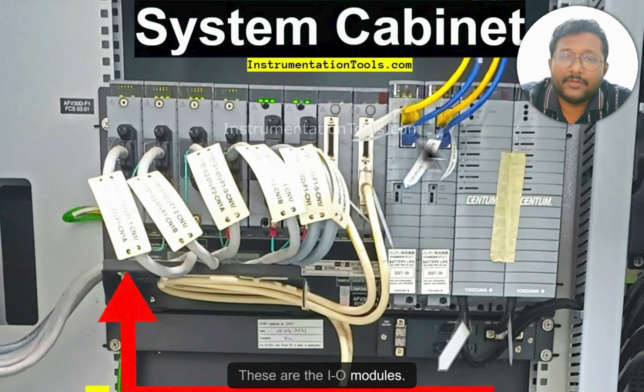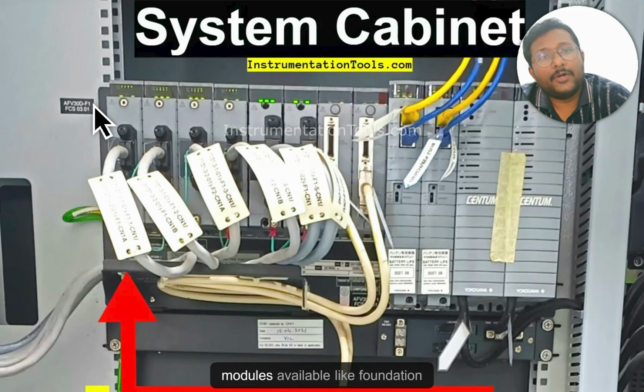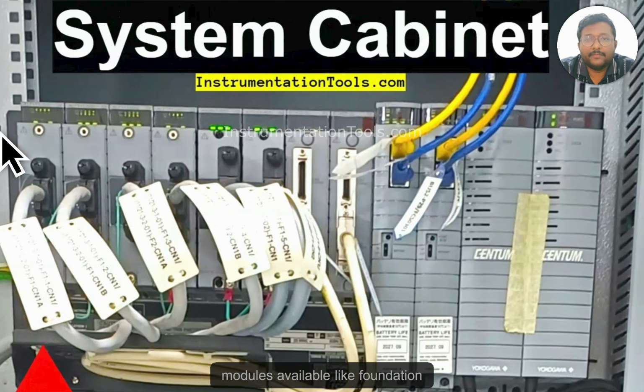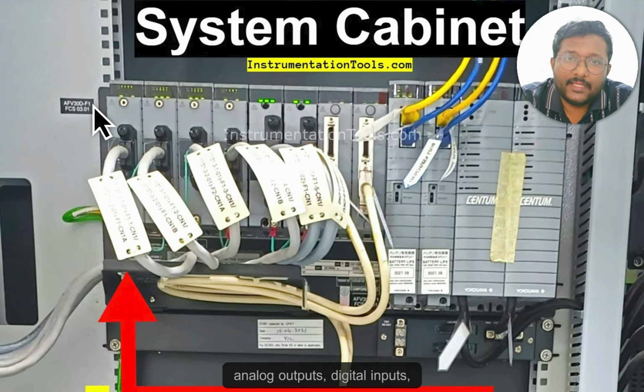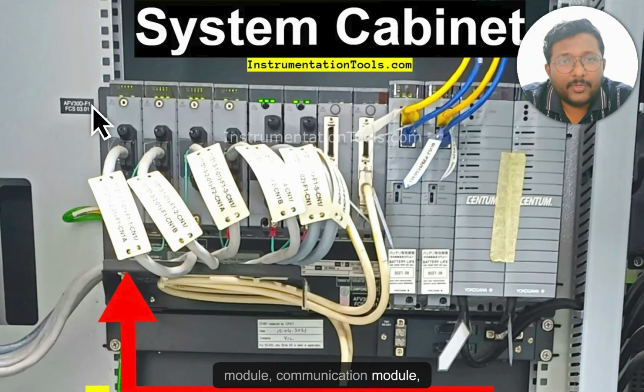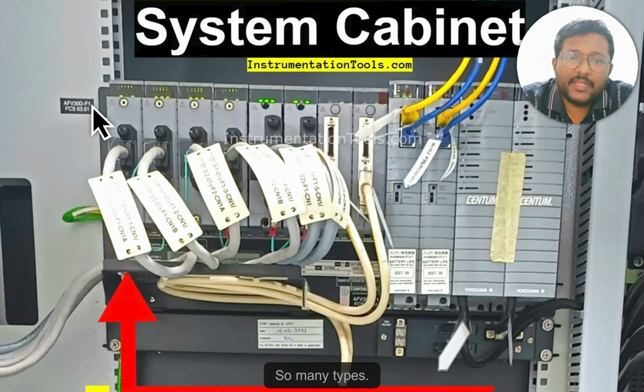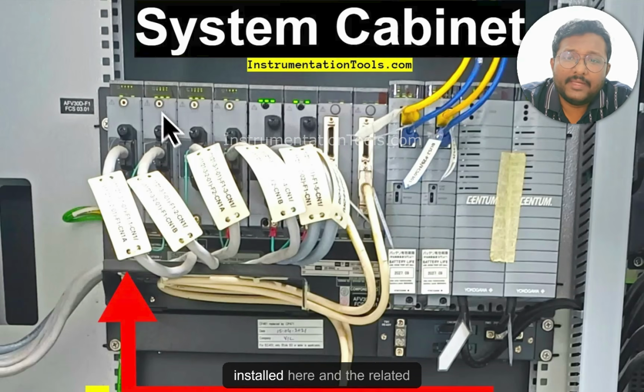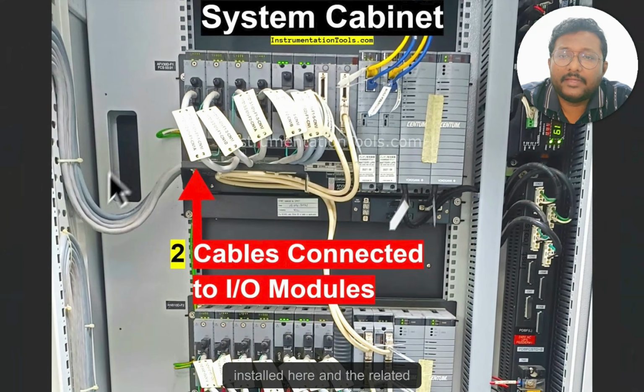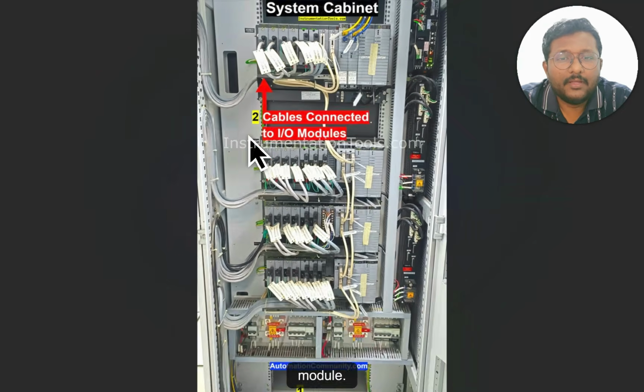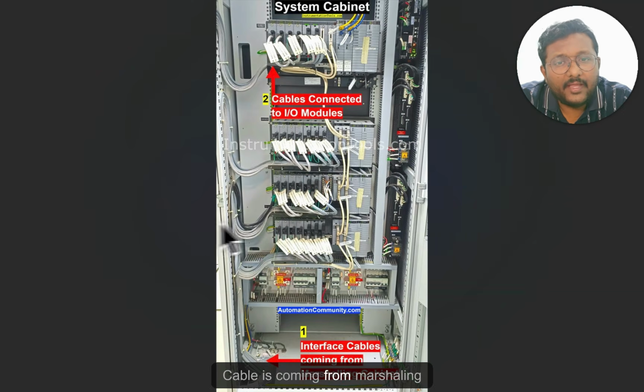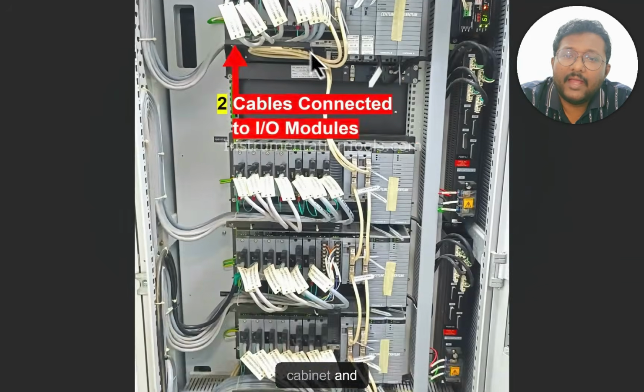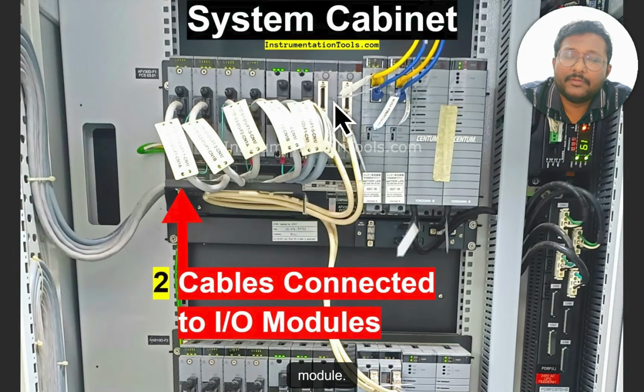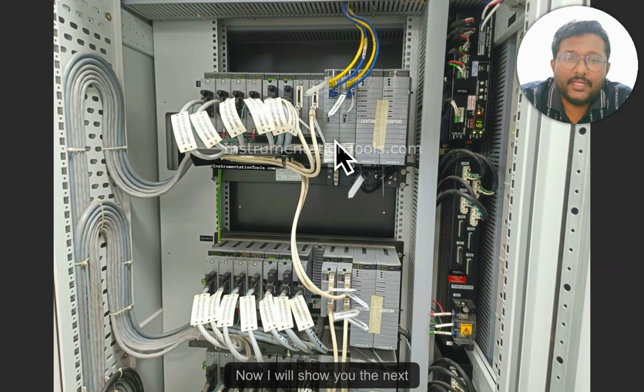These are the I/O modules. We have different types of I/O modules available, like Foundation Fieldbus, Profibus, analog inputs, analog outputs, digital inputs, digital outputs, RTD module, thermocouple module, communication module, Modbus, etc. So many types. The respective module will be installed here, and the related cable will be connected to the module. The cable comes from the marshalling cabinet, enters the system cabinet, and is then connected to the respective I/O module, right? Now I will show you the next one.